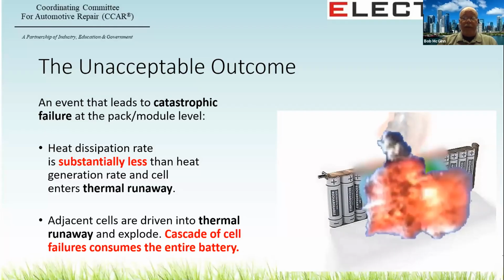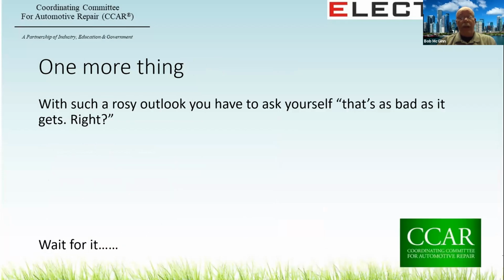To recap, an abuse event occurs within the cell, leads to an increase in temperature. The reaction within the cell creates additional heat and gas, and the reaction zone expands. Heat dissipation is substantially less than heat generation rate over time, and the cell enters thermal runaway. Additional heat and gas are produced. The cell vents violently and explodes, and adjacent cells are driven into thermal runaway and takes the whole battery with it. So with such a rosy outlook, you have to ask yourself, it's as bad as it gets.